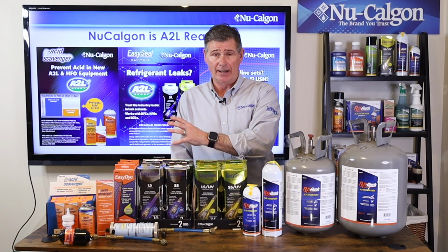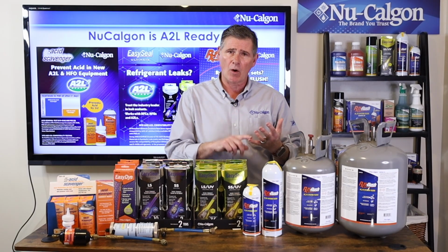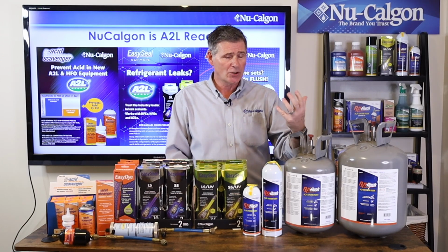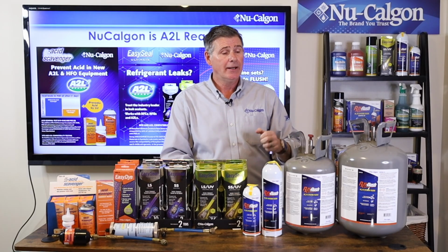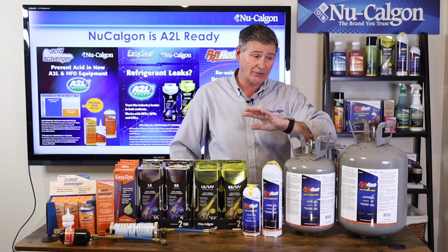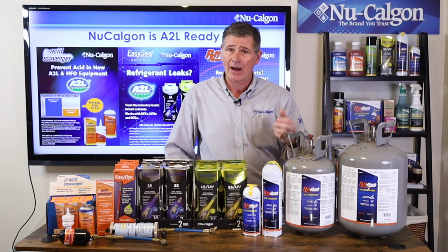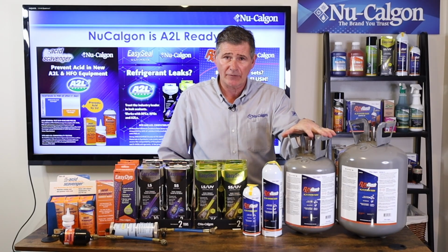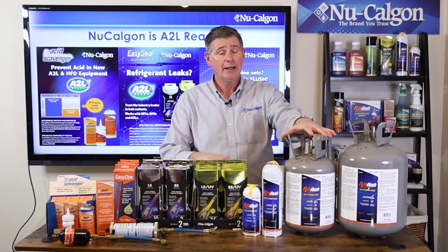Particularly if there hasn't been a burnout, right? So you don't know what's in that system. RX11 is perfect because it will break down carbon and oil and acid and moisture. It will emulsify it, liquefy it, so that it's easily pushed out of the system with nitrogen. Once you button that system up and draw your vacuum, this will immediately begin to boil off. This is an absolutely fantastic product. Because it's a system flush, you can use this even on an evaporator coil to get that all flushed out as well. Again, no residue left behind whatsoever. This is non-flammable, it is non-toxic, and leaves no residue in the system.